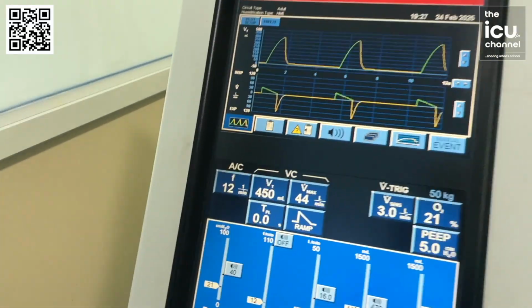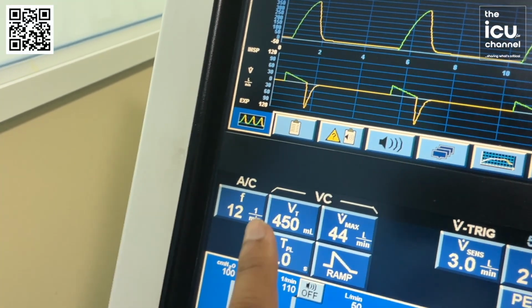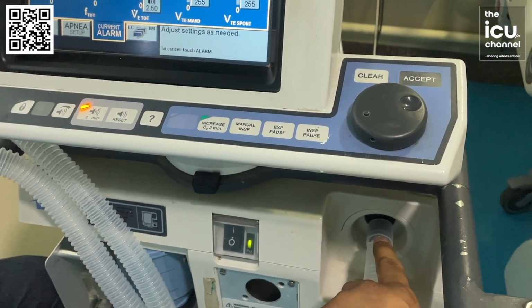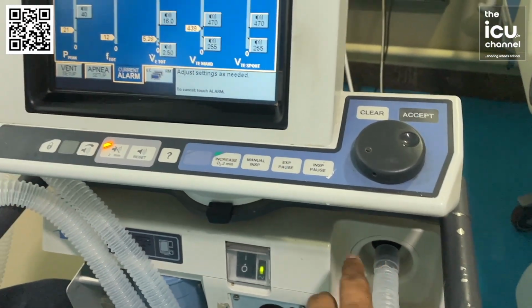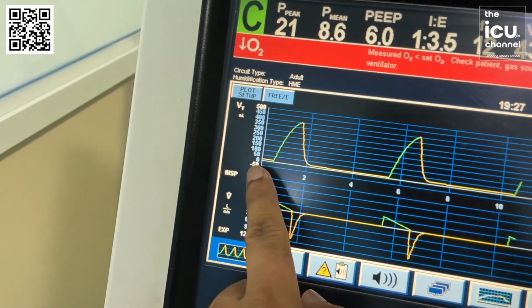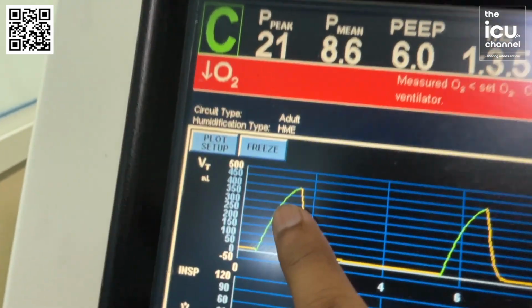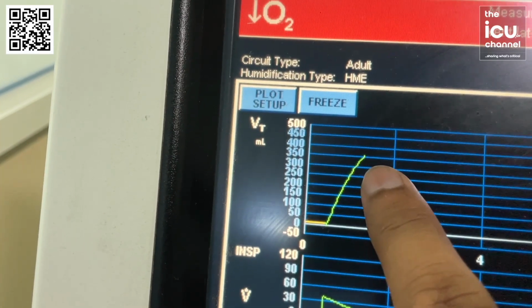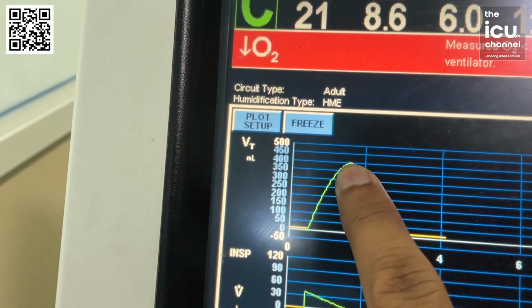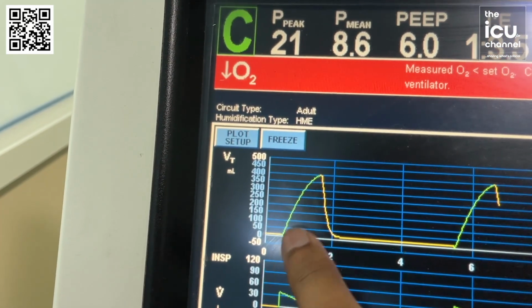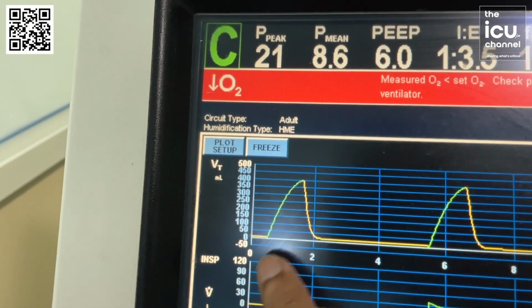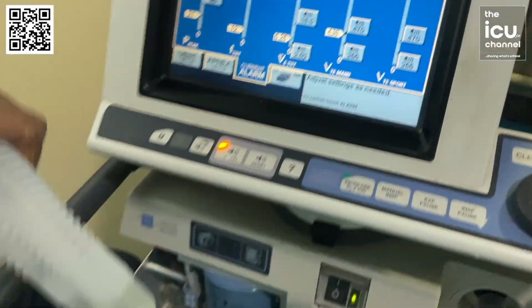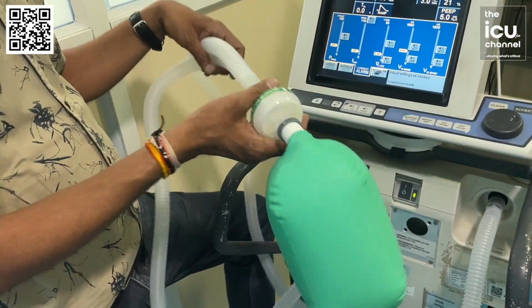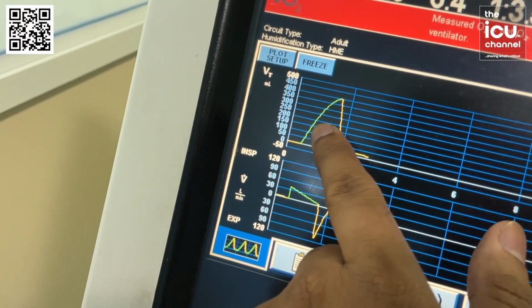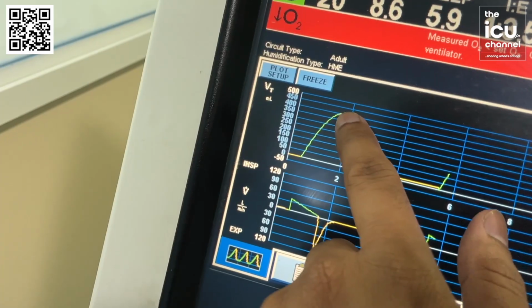Now this 450 tidal volume, how can we see whether the machine is delivering 450 tidal volume or not? We'll see that in the graph, the volume time scalar. You can see that here is the amount 450, and it is touching around 4, a little bit below, but it is approximating the 450 mark. But that means this is the inspiratory limb, this is the expiratory limb. So inspiration is touching 400, 450.